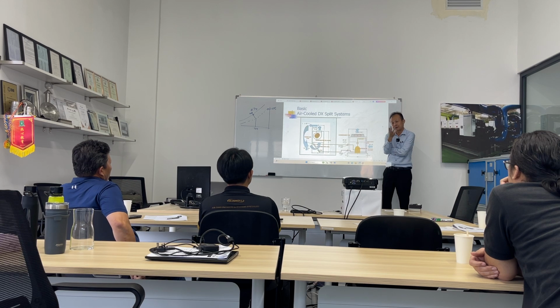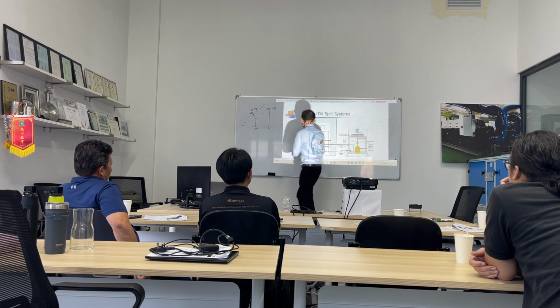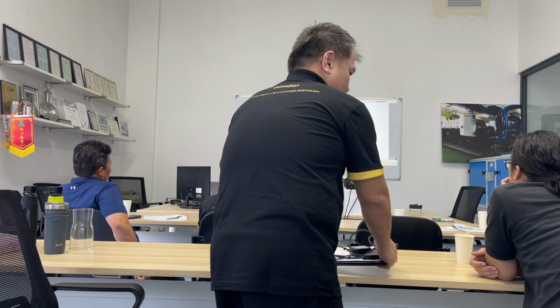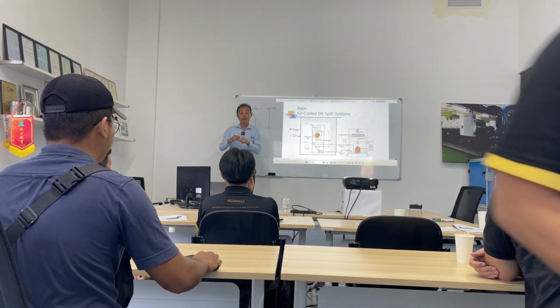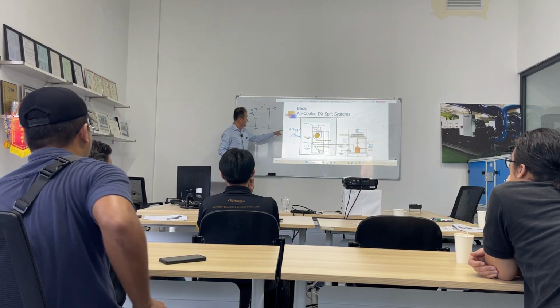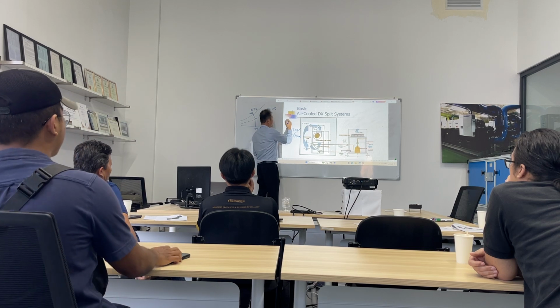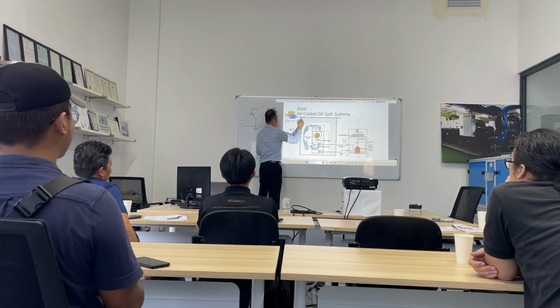Especially nowadays, for all the DX split systems, the supplier's so-called rated standard conditions are not this, no. It's actually 80 degrees F dry bulb and 67 degrees F wet bulb. You look at the catalog, all their standard rated conditions, they call it on-coil temperature.